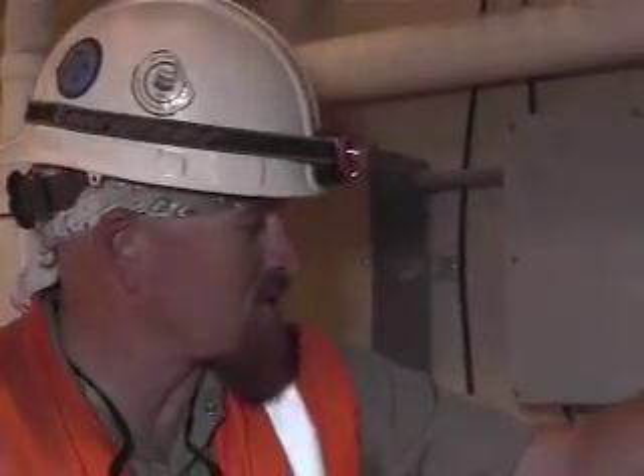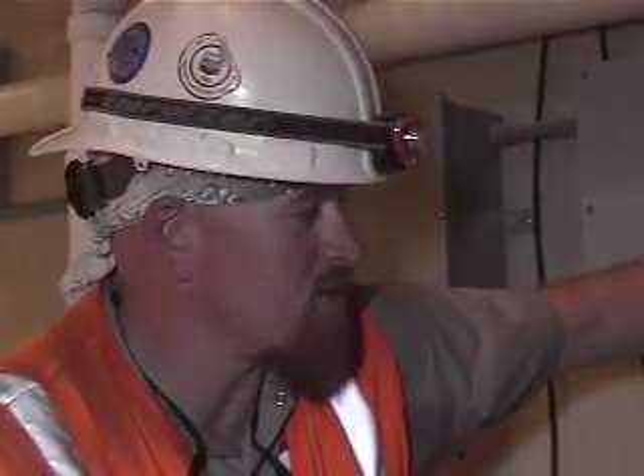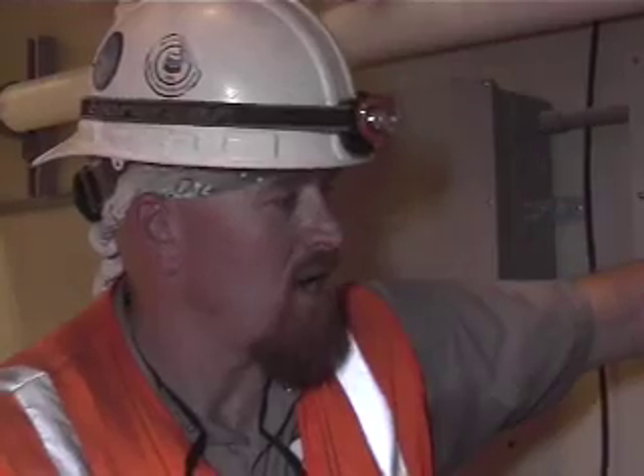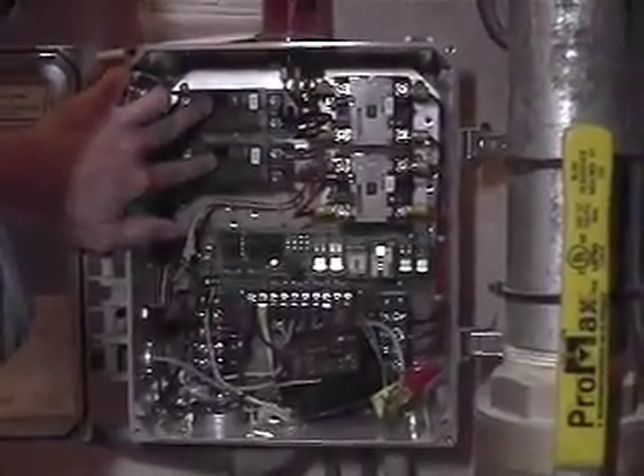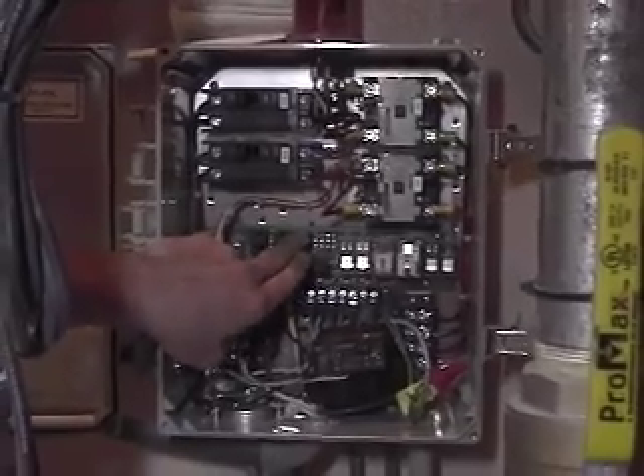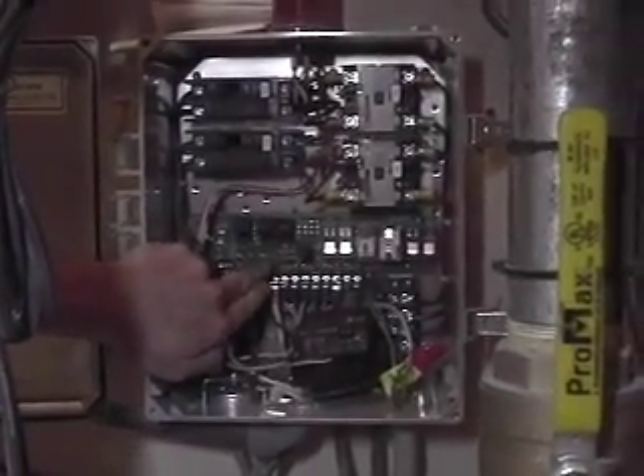Could you talk about the labeling of the circuit on that? Right now, we don't have a label for which circuit breaker actually shuts these panels down. The electricians are supposed to come in and label these to let you know what circuit breaker and panel you'd need to shut these down — that would be control power, 120 volts, and power for your pumps, which is 208. You can shut your 208 power off to the pumps with these two circuit breakers, and your control panel is this switch here. You saw that LED — it's off right now, and now it's back on.